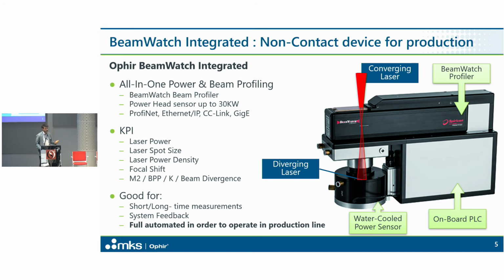The KPIs, the key performance indicators, I told you: laser power, spot size, waist position, waist size, and propagation parameters like M square, divergence, and so on. For what is this good, I will highlight here long and short time measurements, because you can install and use it for a very quick understanding or a pass-fail between each job measurement session, or you can use it for a long-run session because you have a fail and you want to investigate deeper what's going wrong.